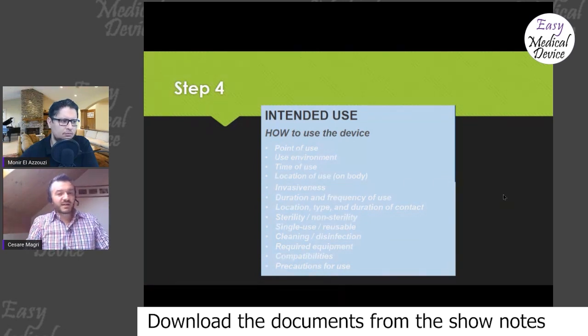You can also specify with which devices your device is compatible, so you should only use it with this type of device. For example, if you build hardware that needs to be used in combination with another medical device, but only with certain models, or only with models that abide by some specification, here you can specify that. And you can also have some warnings, some precautions of use that are really clinically relevant. You don't have to include all the warnings from the user manual, but definitely those that are very important for clinical use. For example, don't use the device if the skin is red. That's a clinical warning. Be careful of that.